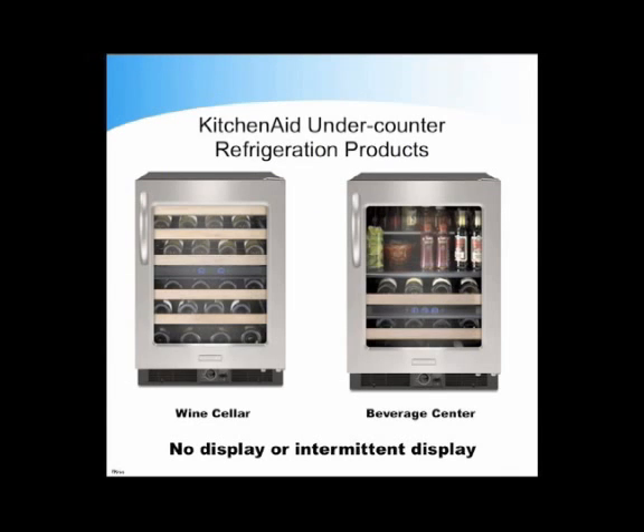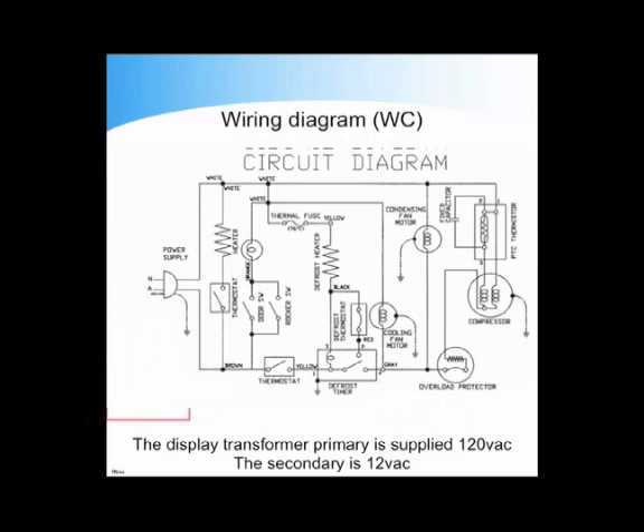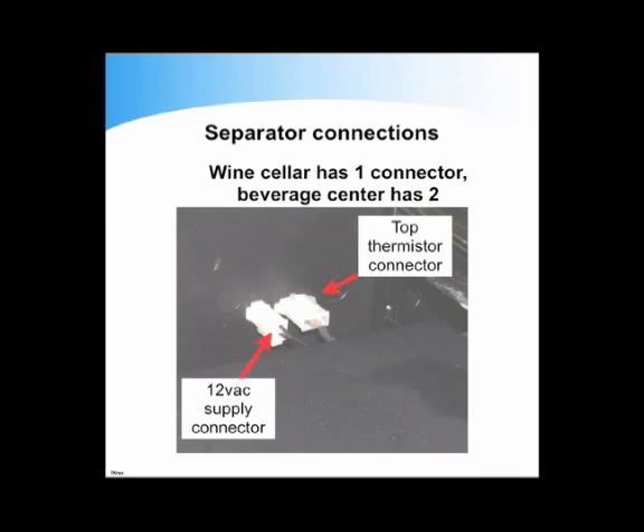KitchenAid under-counter refrigeration products: some wine coolers and beverage centers have had no display or intermittent display. Wiring diagram, WC. Check for 12-volt AC output from the transformer. The display only displays. It has nothing to do with temperature management. Separator connections: the wine cellar has one connector. The beverage center has two. Remove the lower rack to access the separator at the rear wall.